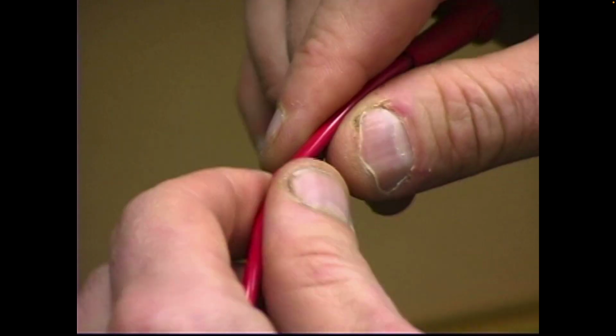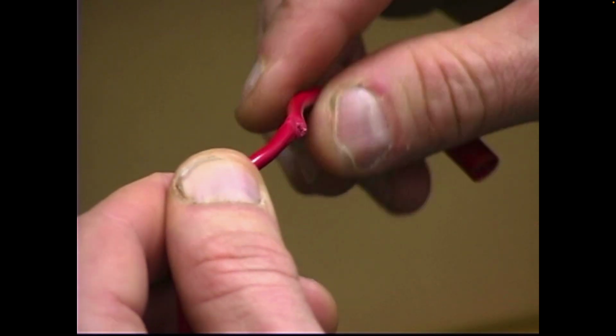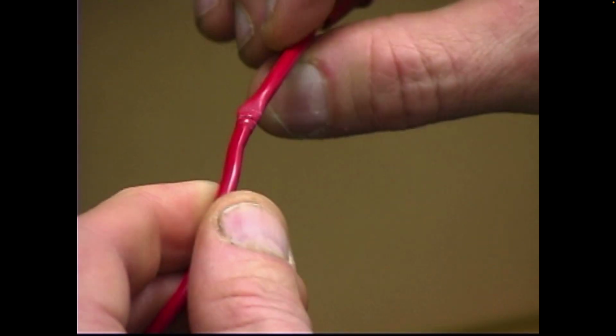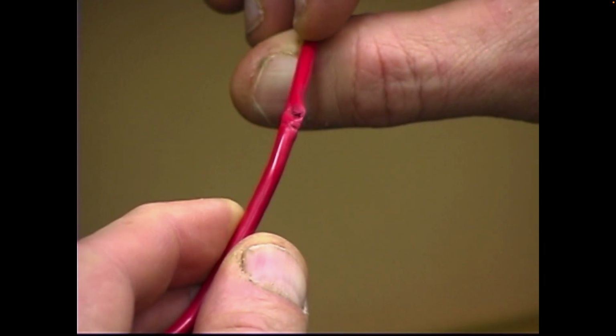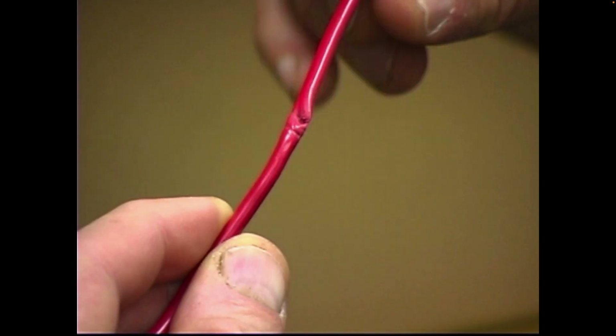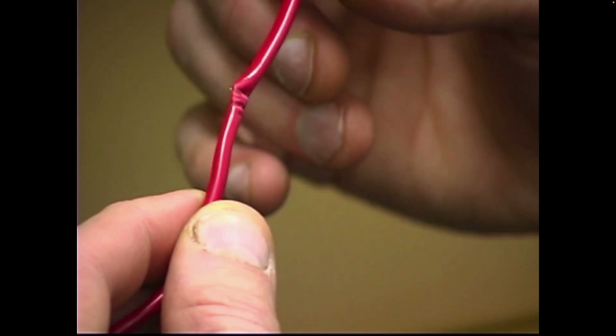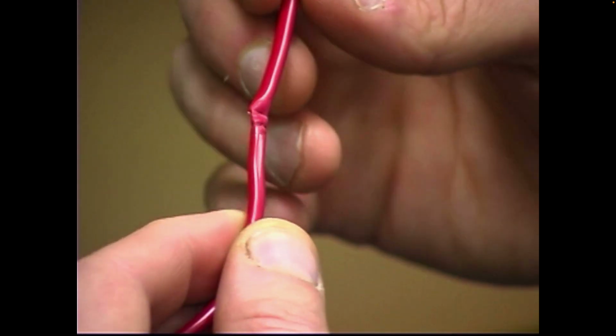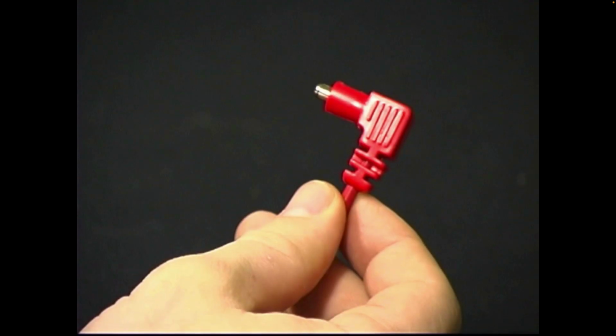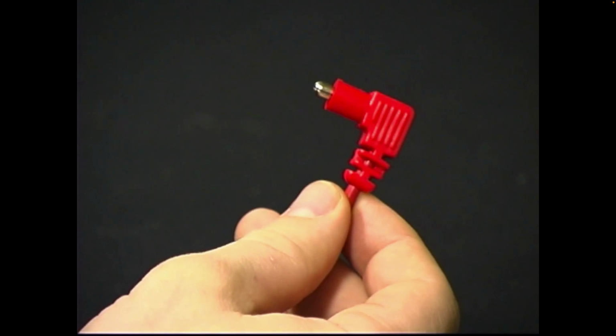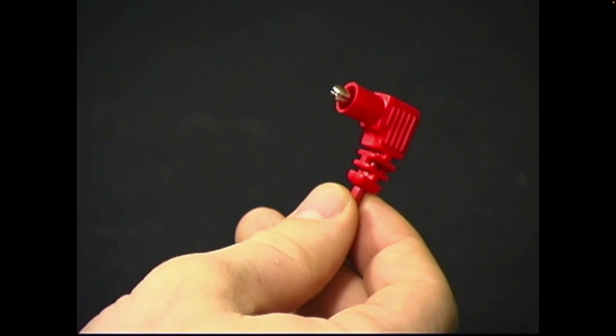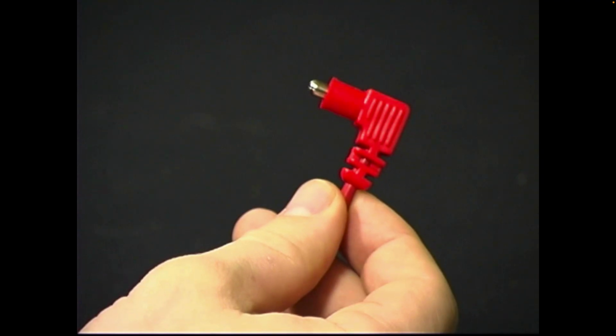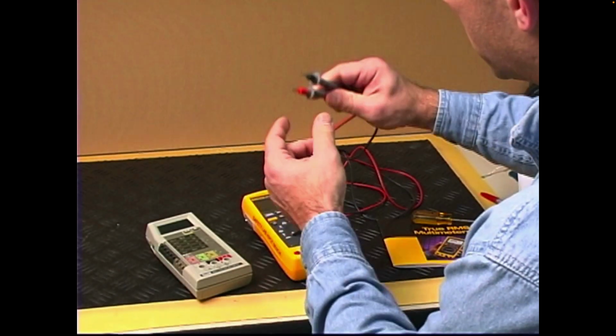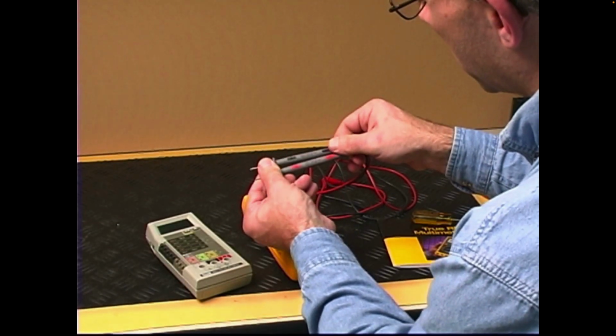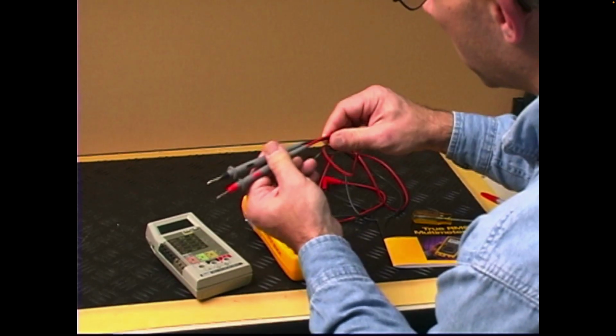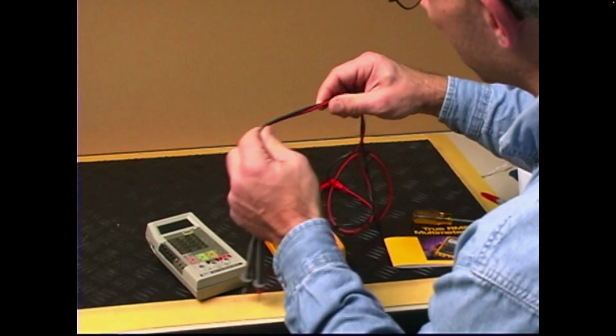Test probes and other accessories can also contribute to danger. Test leads can become frayed or come out of the meter jacks. If the probe tip is connected to 480 volts and a nicked or underrated test lead comes in contact with another conductor, a fault may result. The same thing can happen if an unshrouded test lead comes out of the meter and touches a conductor. Make it part of your routine to inspect your meter and its test probes before using them. Please refer to the guidelines provided at the end of this video on what to look for.